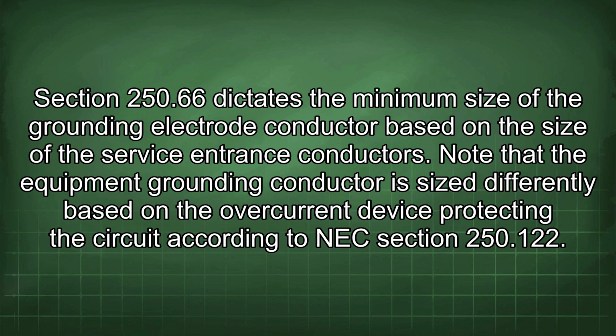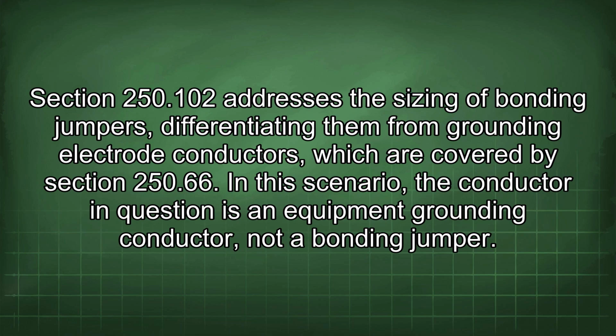Section 250.66 dictates the minimum size of the grounding electrode conductor based on the size of the service entrance conductors. Note that the equipment grounding conductor is sized differently based on the overcurrent device protecting the circuit according to NEC section 250.122. Section 250.102 addresses the sizing of bonding jumpers, differentiating them from grounding electrode conductors, which are covered by section 250.66. In this scenario, the conductor in question is an equipment grounding conductor, not a bonding jumper.